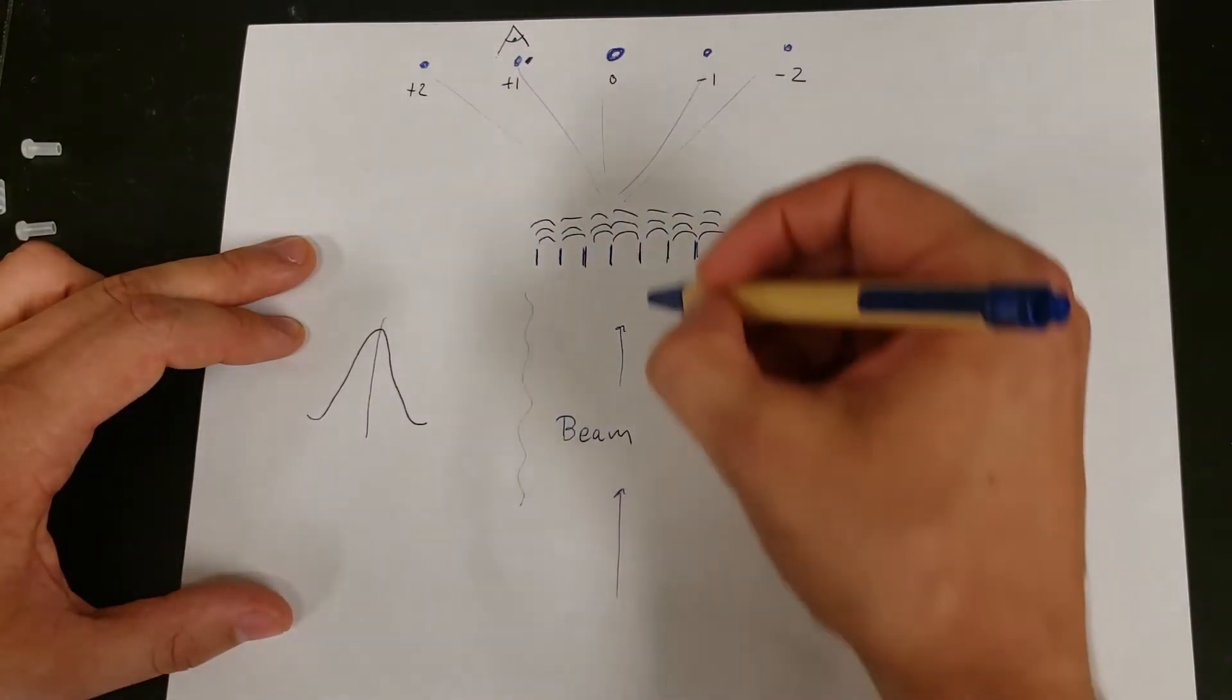And if you have a beam coming in, it simply measures the amount of power that's created in, let's say, the first order here. Now what's interesting is that if you have a single wavelength coming in, it's going to create this blue spot right here. But if you have a different wavelength as well inside of the beam, being that you have two different colors, then that other color is going to create an interference point slightly separated from this one. So in other words, in order to measure the whole spectrum, all the OSA needs to do is take the beam coming in and then record the amount of power that it has for this particular orientation of the grating. Then you can simply rotate the grating slightly, and what's going to happen is that this blue spot here is going to shift to the left, and then the black one right here will come into view. Then we also can measure the power of this one and then just rotate the grating a little bit more. And then we can measure the next color that comes into view and its strength.